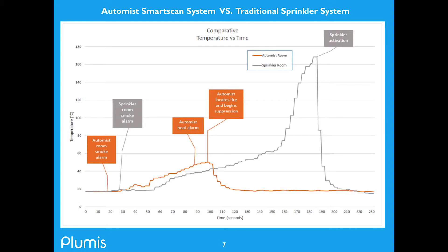The thing that the insurance folks were amazed at is this was a chair fire that a sprinkler basically controlled perfectly and put out. This also was controlled perfectly and put out by Automist, and that was the damage that was left. And I would defy you to come up and take a look to see where most of the damage is, because it was so early that it typically works very, very quickly. So this is how this works.